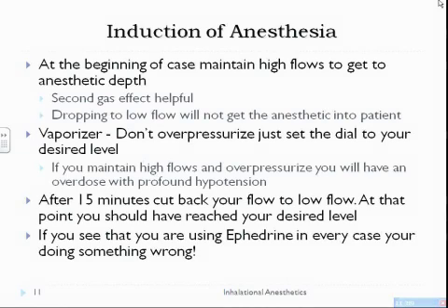With the vaporizer, please don't overpressurize unless you're doing it for a reason. Just set the dial to the MAC that you want, and then it gets you there. If you want to overpressurize, that's appropriate, but keep your hand on the dial. That way you know that you're not going to walk away and kill the patient. Okay, because you will hurt somebody if you're not careful.